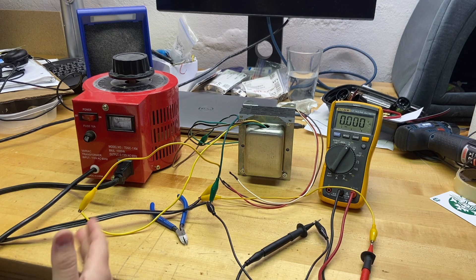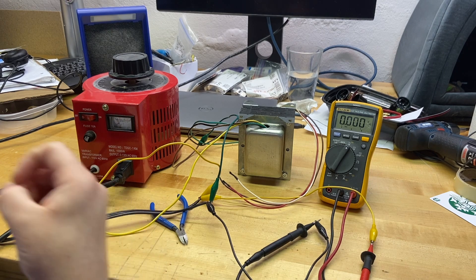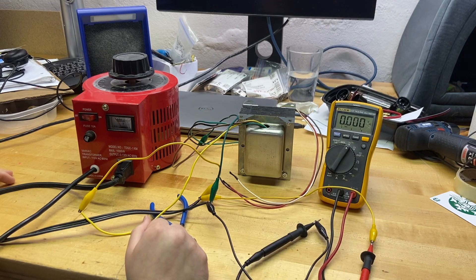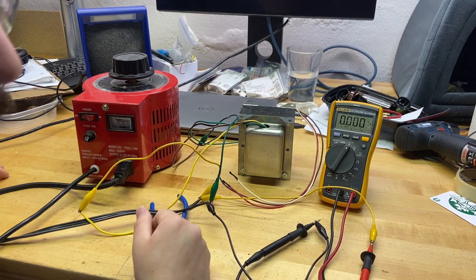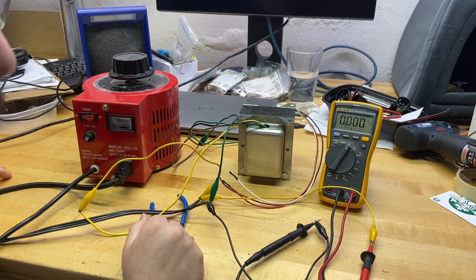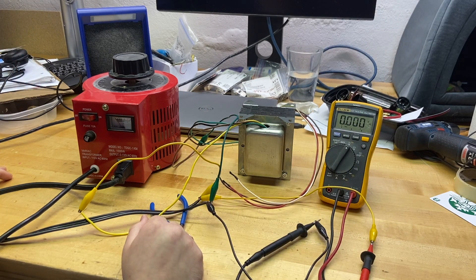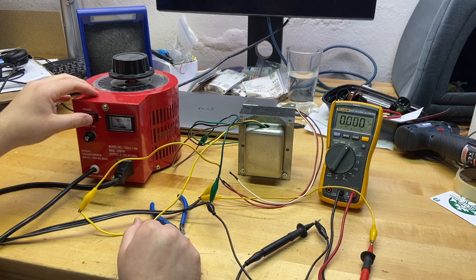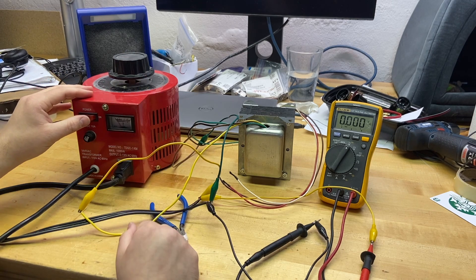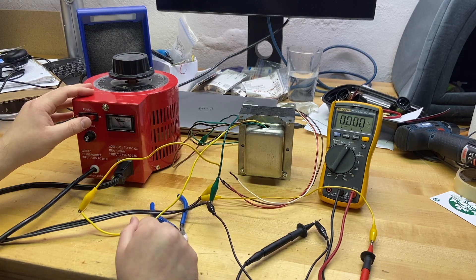Neutral's hooked up to black lead here. Red lead's hooked up to line. Polarity doesn't really matter here, but it's nice to keep it in mind at all times. So again, a good transformer. If I flip this switch, we should just see 3.25 volts AC, and we validated that the transformer is good. Well, with one caveat, but let's get to the test.